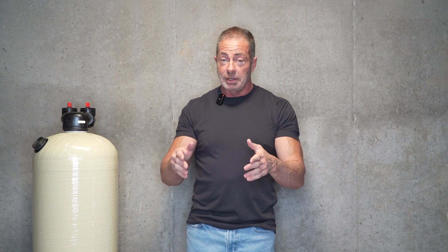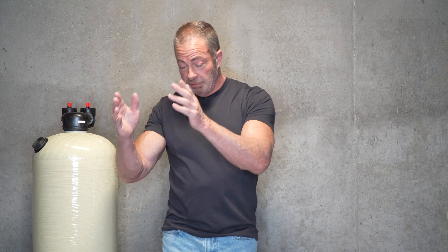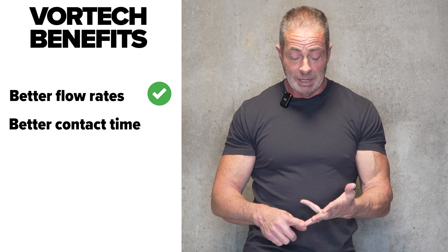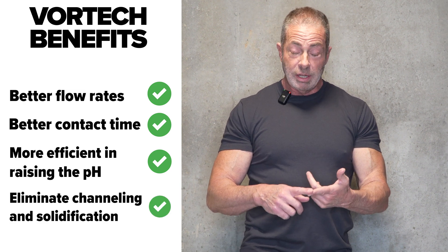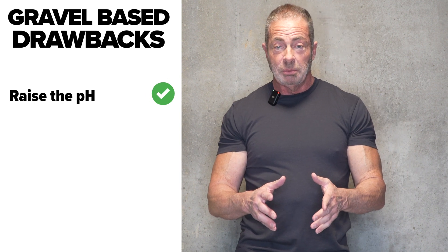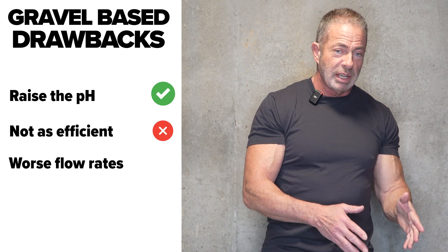Now that I've explained both units, I hope that makes it easier for you to decide. With the Vortech unit, you're going to get better flow rates, better contact time, it's going to be more efficient in raising the pH, and it's going to eliminate any possibility of channeling and solidification. With the gravel-based unit, it's going to raise your pH, but it's not going to be as efficient and you're not going to get the same flow rates.